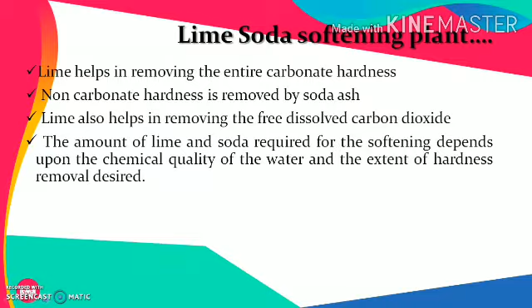Generally, the lime and soda ash requirement can be estimated using these rules. For 100 mg per liter of CaCO3 alkalinity, it needs 56 mg per liter of lime. In case of MgSO4, if the presence is in the range of 120 mg per liter, it needs once again 56 mg of CaO or the pure lime and 106 mg per liter of soda. 110 mg per liter of CaCl2 needs 106 mg per liter of soda.